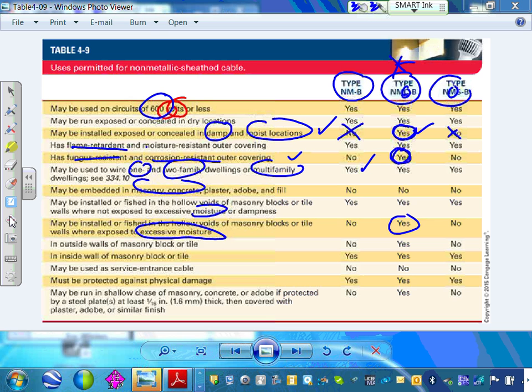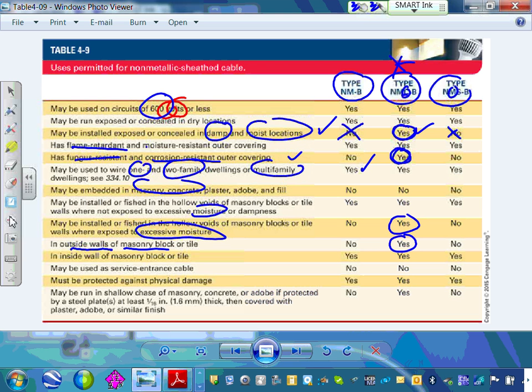The UF, guys, is underground feeder. This is just above ground feeder for excess moisture. It's just in outside walls or masonry. Look at that. If you put it in an outside wall or masonry block, look at the one that stands all the time, the one that has a C. Outside walls, inside walls, no problem. I'm trying to pinpoint that this is a higher grade one for excessive moisture and damp location.